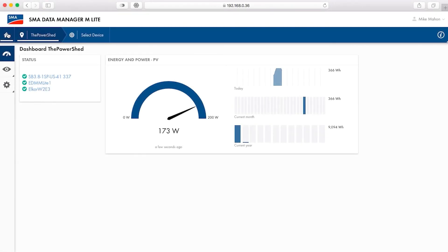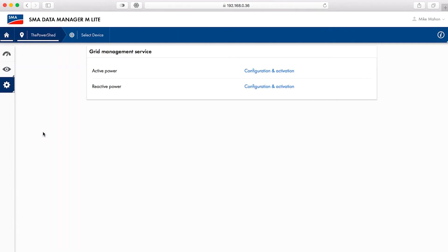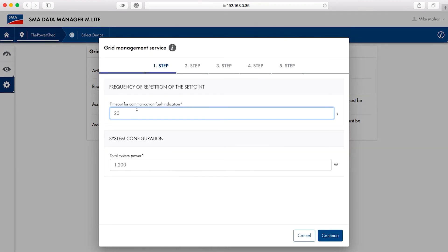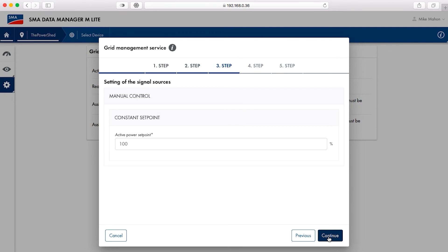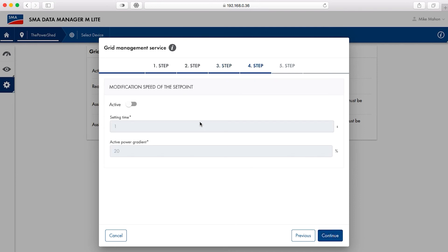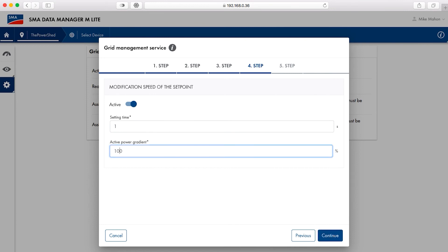Now we are ready to configure the settings for the specific export limitation scheme. Select the home icon at top left in the Data Manager M Lite user interface. From the configuration menu, select grid management service. On the window that appears, select configuration and activation across from active power. In step one, set values for timeout and verify the total system inverter AC power. Select continue when done. In step two, select closed loop control and manual control, then select continue. In step three, set the set point for export. Zero is correct for zero export. A positive percentage of total AC power should be selected for export limitation. A negative number can be set if net power should always be drawn from the grid. Select continue when done. In step four, click the slider next to active and set the settling time and active power gradient. Often one second and 100% are appropriate values.